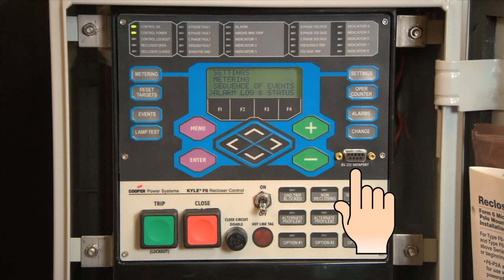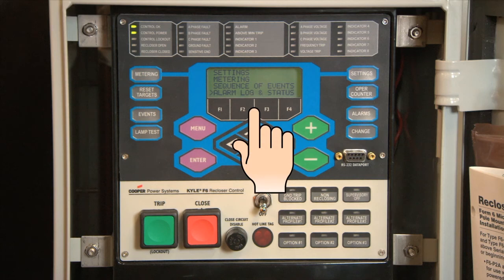The interface program software includes additional functions used to create and graphically display time current curves and provide IDEA workbench for configuring user-selected inputs and outputs, configurable event and alarm data, and selectable communication points for serial communication. The control operates on 50 and 60 Hz systems. The control can be configured by the factory or by the user for a wide variety of applications. If user requirements change, the control functions can be modified to meet the new requirements.